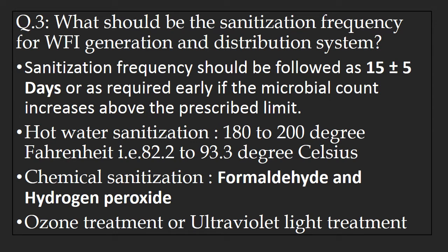In the case of hot water sanitation, WFI at 180 to 200°F (82.2 to 93.3°C) is circulated through the system. In the case of chemical sanitation, chemicals like formaldehyde or hydrogen peroxide are used to sanitize the water system.